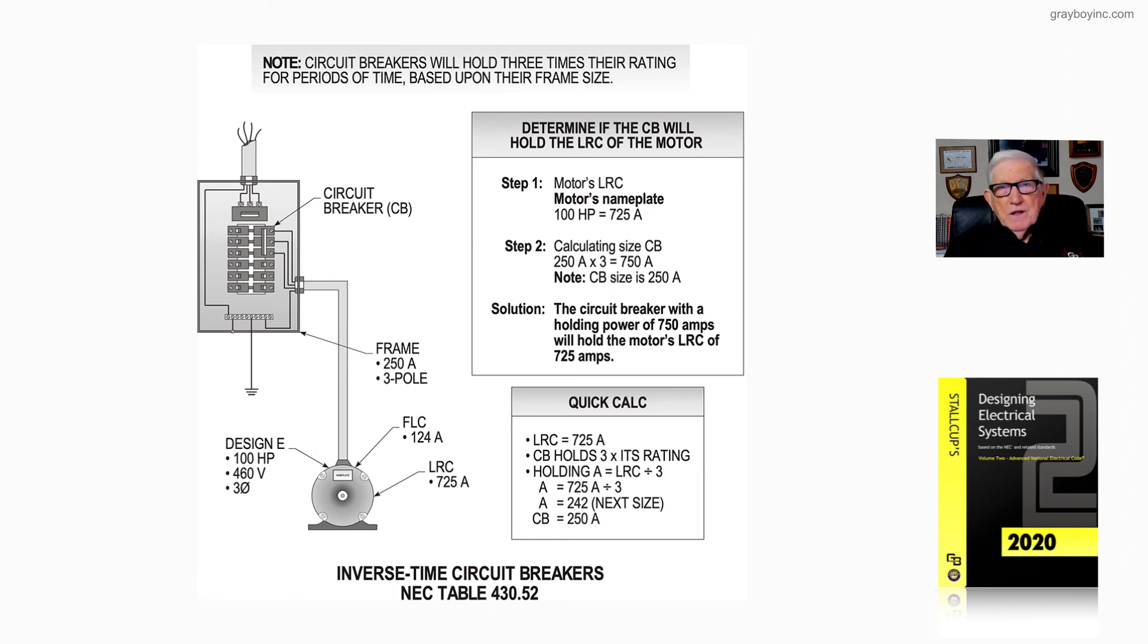The code just gives you maximum and minimum values. Table 430.52 is just giving you a percentage to start with. You can always round it down, but you can't round up without having an exception to let you do so. That's important for engineers and electricians to understand.